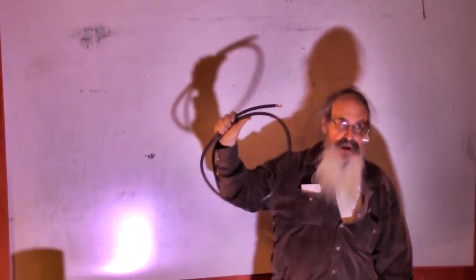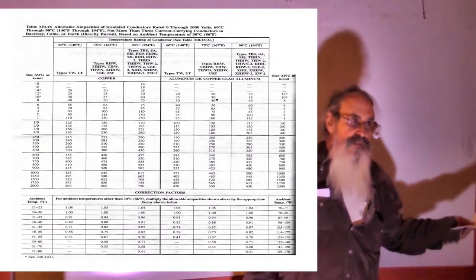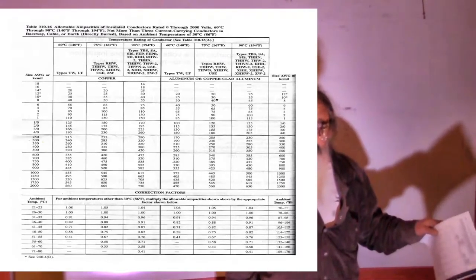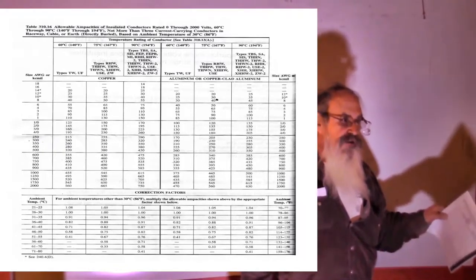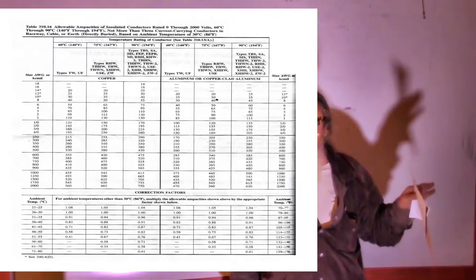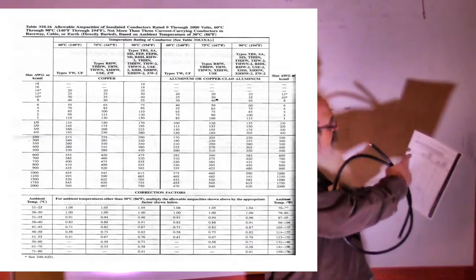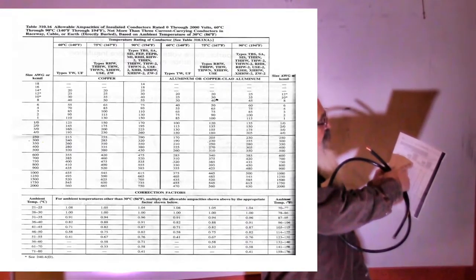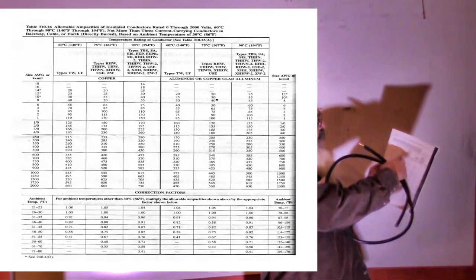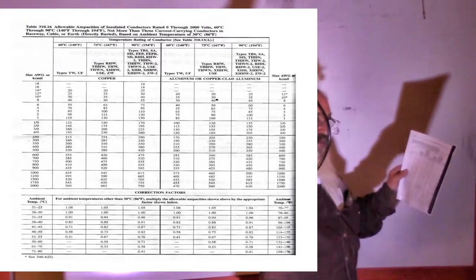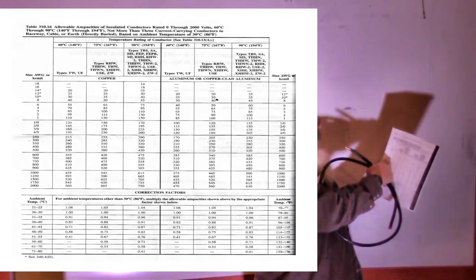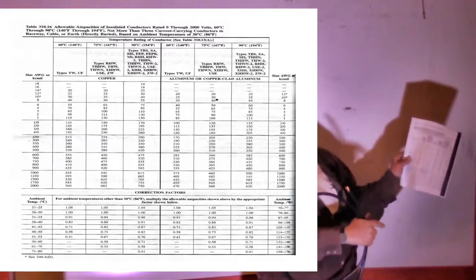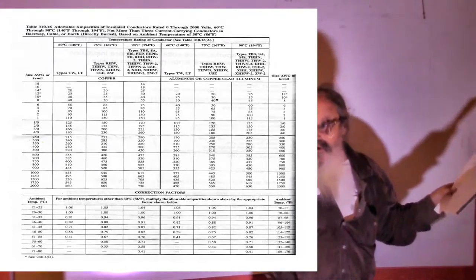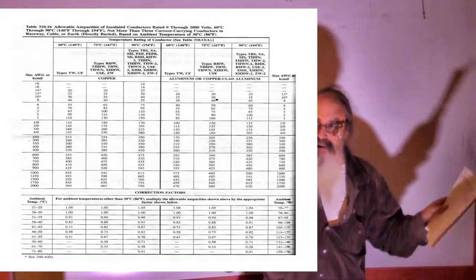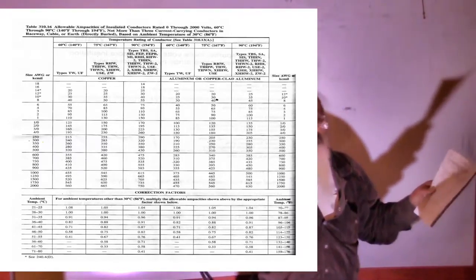This is 10 gauge, type THHN. If you look on the other side of the crib sheet, you'll see something I just photocopied out of the National Electrical Code. This is the Code's version of how many amps you can run through a piece of wire. If you look at the 4th column over, that's for type THHN, which is this type of wire. If you look down the first column, that's the wire gauge, AWG, American wire gauge, also called gauge or number. Like this, you get number 10 wire, number 12 wire. That's AWG.